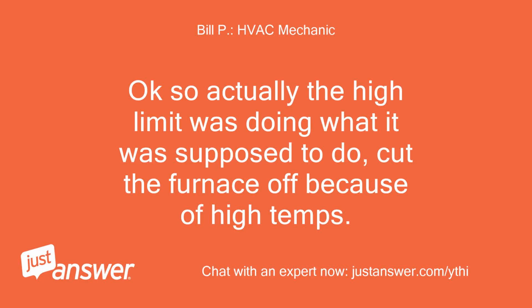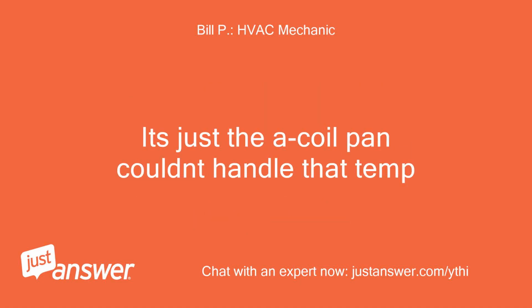Okay, so actually the high limit was doing what it was supposed to do, cutting the furnace off because of high temps. It's just that the A-coil pan couldn't handle that temp.